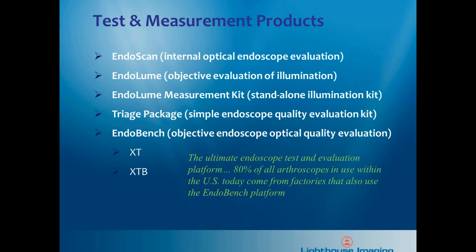So next up we have the EndoLume measurement kit. This packages the EndoLume with a light source and a light cable. For the biomed or central sterile technician, they typically don't have access to these other components. So if you wanted to test a light cable, you would need a light source to do that, or if you wanted to test an endoscope, you'd need a light source and a cable to hook up to it. Surgical light sources and medically rated cables are fairly expensive and not often just laying around in a biomed or central sterile department. So the EndoLume measurement kit packages these together for their use.